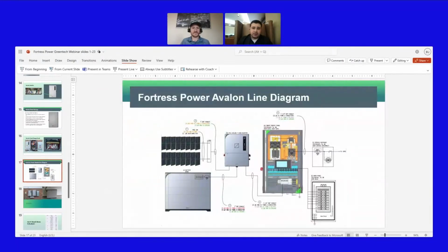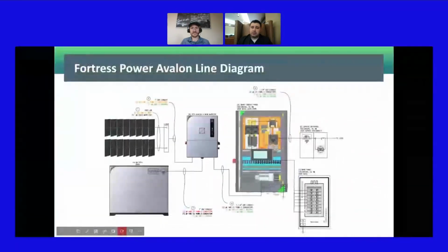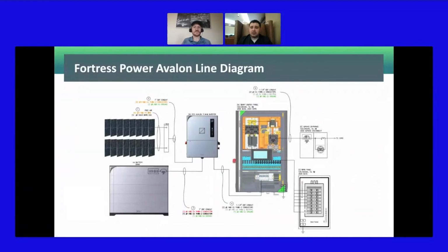I see some questions here, some of which I responded to in written form in the chat. The one I was typing a response for was from Jeff: what are the parameters associated with the SOC set points? Are there time delays, deadbands, etc.? When configuring load shedding using the phone app or web app, you specify for each load what battery percentage interval it's allowed to operate in. For example, you might not want your EV charger to come on if the batteries are below 40%, so you can specify the battery SOC range from 40 to 100. For something else, you could set it from 50 to 70. It's completely arbitrary.